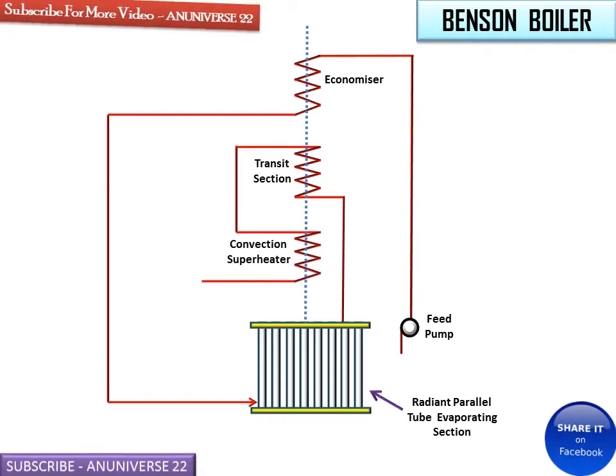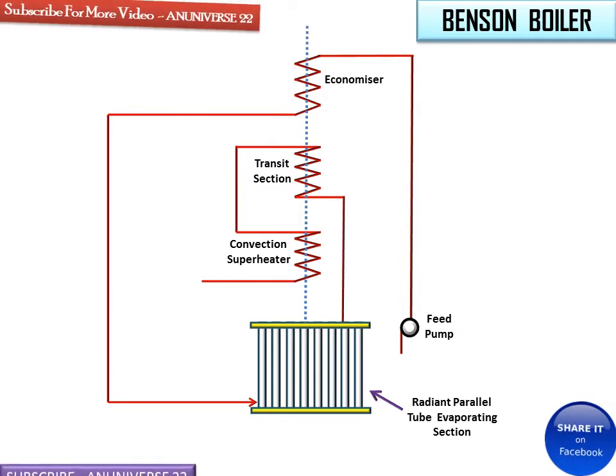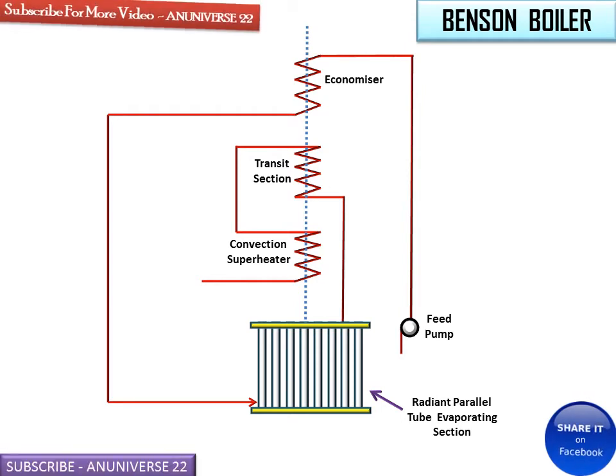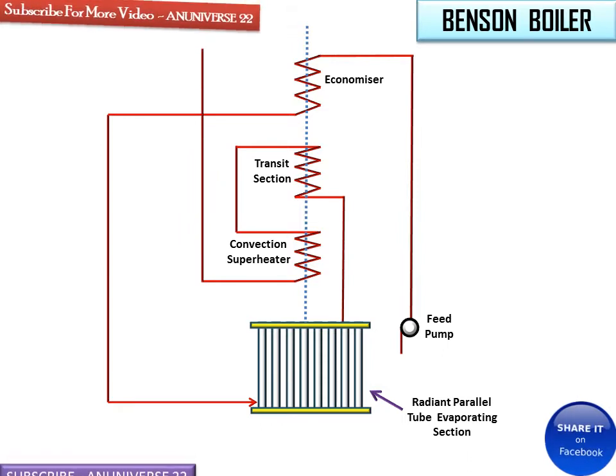Finally, it is supplied to the convection or convective superheater, which is the last chamber of the boiler. The saturated steam coming out from the transit section is supplied to the convection superheater, which increases the temperature of the steam. This superheated steam at about 650 degrees Celsius is taken out for industrial work and moves to the prime mover.